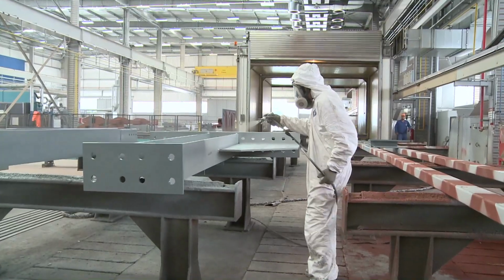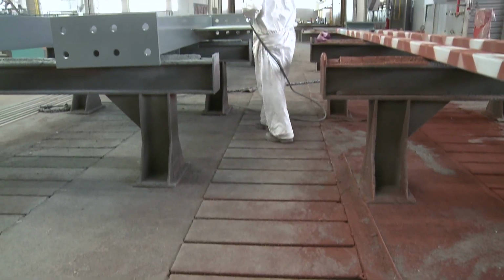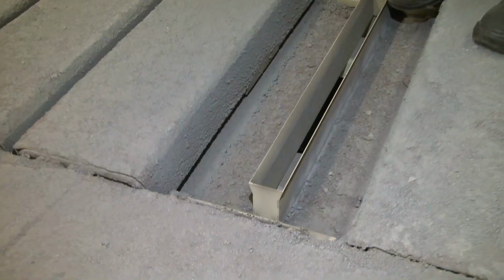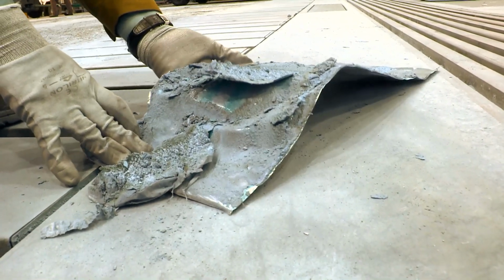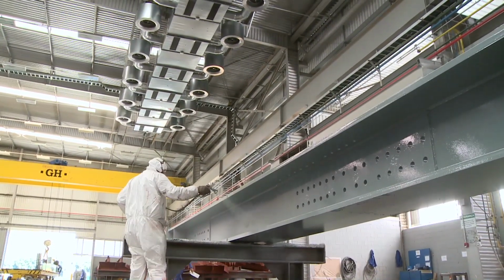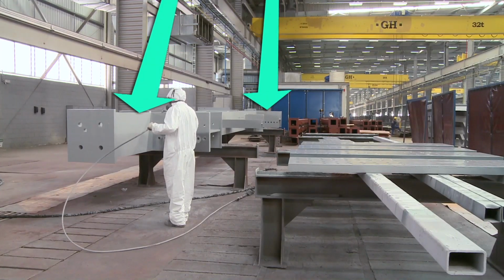For these reasons, we developed so-called heavy load impact separators for this application. The floor profiles are designed to handle wheel loads of 30 kilonewtons. As it falls downward, the excess spray fog is redirected several times by the interlocking profiles, with the overwhelming majority of the overspray settling on the collection plates. At the appropriate time, the thin steel plates which serve as the upper and lower overspray collectors are replaced or cleaned. The incoming air from the long-range nozzles and the suction force from beneath the impact separators combine to produce the desired air settling speed of 0.3 meters a second in the particular work area.